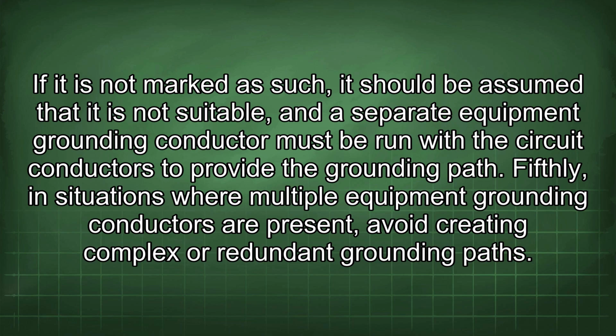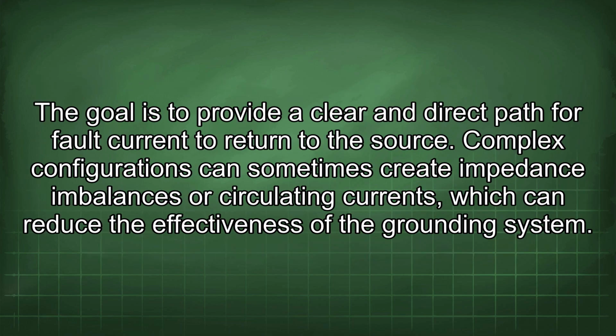Fifthly, in situations where multiple equipment grounding conductors are present, avoid creating complex or redundant grounding paths. The goal is to provide a clear and direct path for fault current to return to the source. Complex configurations can sometimes create impedance imbalances or circulating currents, which can reduce the effectiveness of the grounding system.